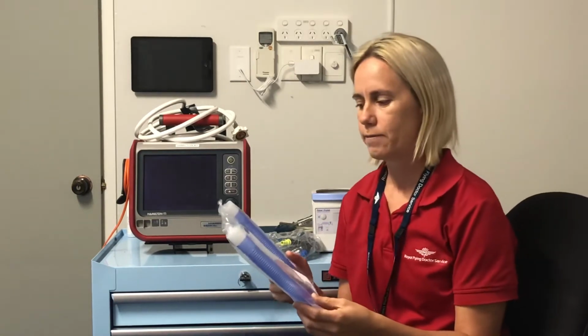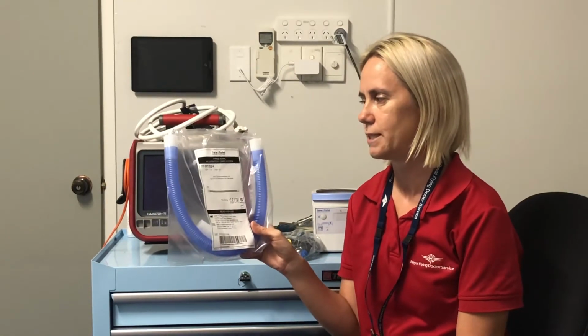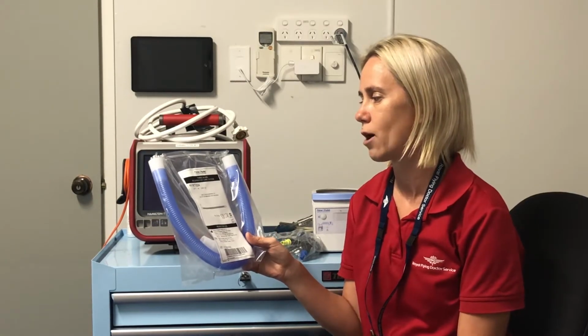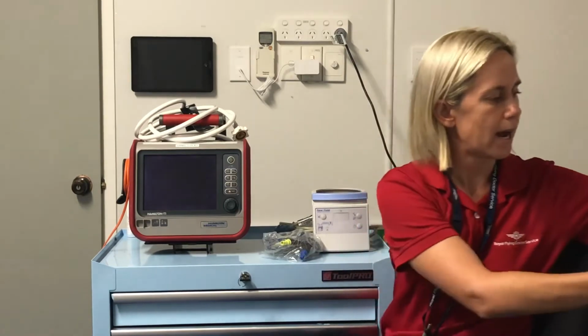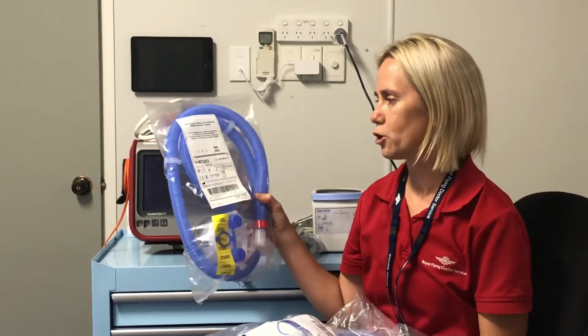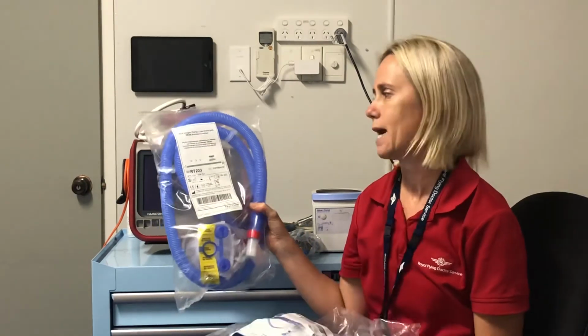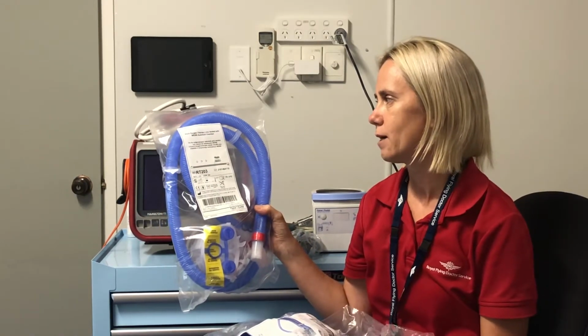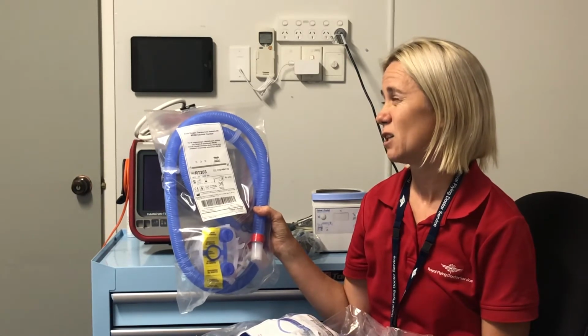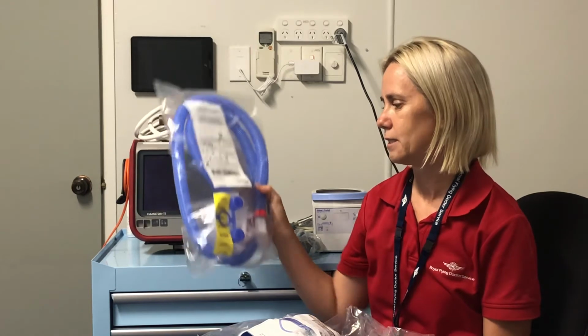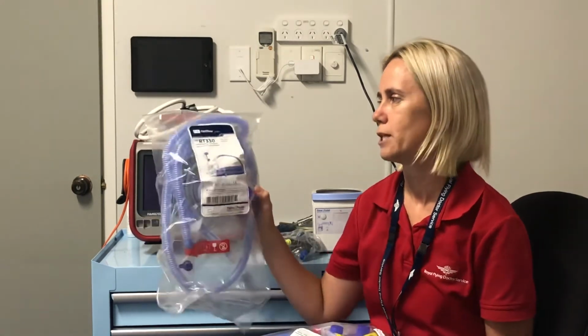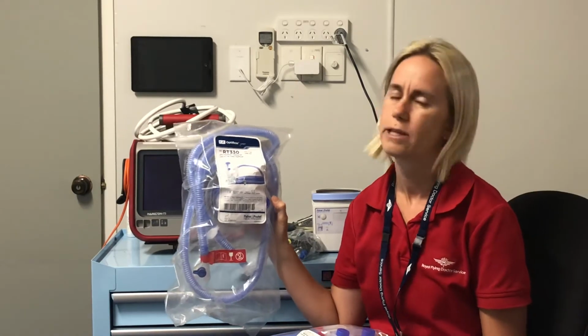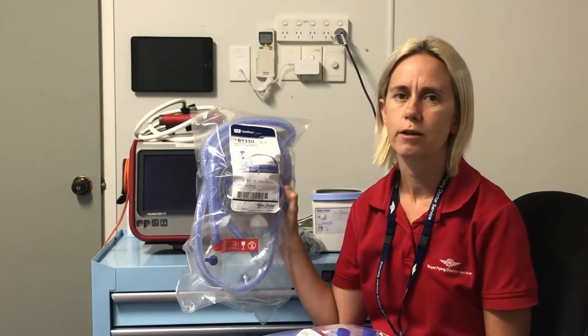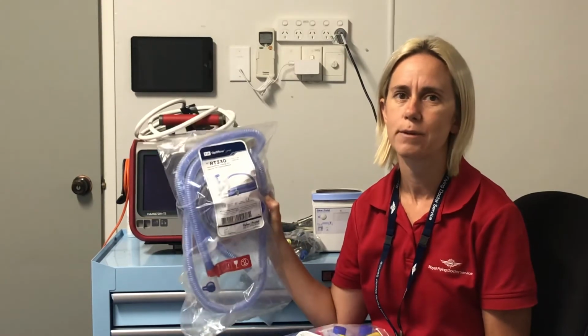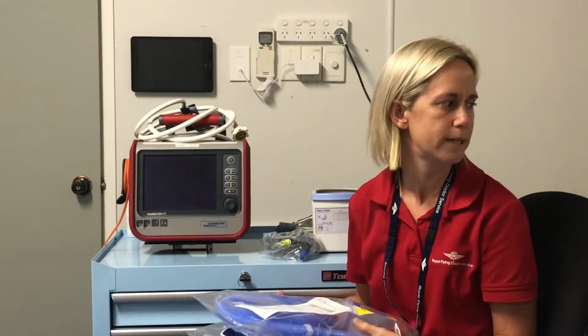I'll just run through what is in the bag, so what also is required. So for my flight nurse, they'll need one of these, which is the RT024, which is the dry extension kit to commence that, as well as we've also got two pieces of equipment, which is for the adult or the pediatric patient. So we've got the RT203, which is the humidified line used for the high flow, and that is used for the adults. And then we've also got the pediatric patient high flow line, which is the RT330, which is more for patients requiring flow rates under 25 litres per minute, where the adult is over 25 litres per minute.